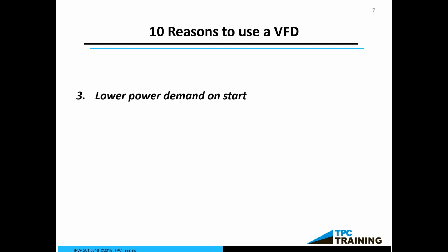Lower power demand, or sometimes they call it demand factor. When you start a large pump, blower, or motor at a large facility, maybe a large manufacturing facility, you can get charged a demand factor or a demand charge. Having said that, did you know, and I'd like you to write this down, there's 746 watts in a horsepower. So do me a favor and write that down. 746 watts in a horsepower.